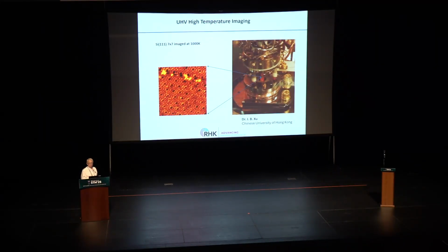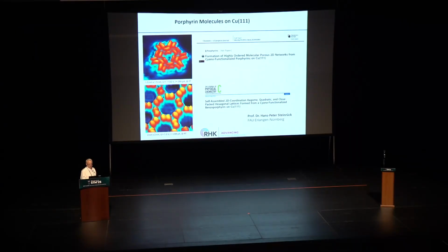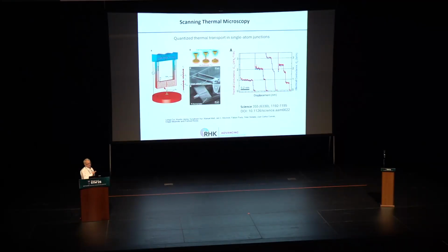Here's an example of working at elevated temperatures. You can see the sample really is glowing red hot. It's at 1,000 Kelvin, and once you reach thermal equilibrium, it can still scan over the same feature with atomic resolution. There are a couple hundred Beetle microscopes around the world, used by many, many different groups. For the cantilever-based version, one unique capability is the geometry of the optics: the laser, the cantilever, and the detector all scan together, so it acts like a sample scanning AFM.